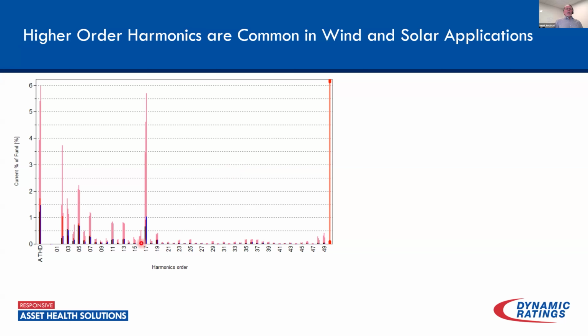And of course, as you increase the harmonic, the frequency of that harmonic is increasing. So the thermal stress and the aging stress associated with those harmonics is going to increase. So again, when compared to traditional applications, the transformers in these renewable applications, and really data centers, fall into the same category. They're being stressed. They're seeing a lot more impact from harmonics than what we have historically seen in the past.